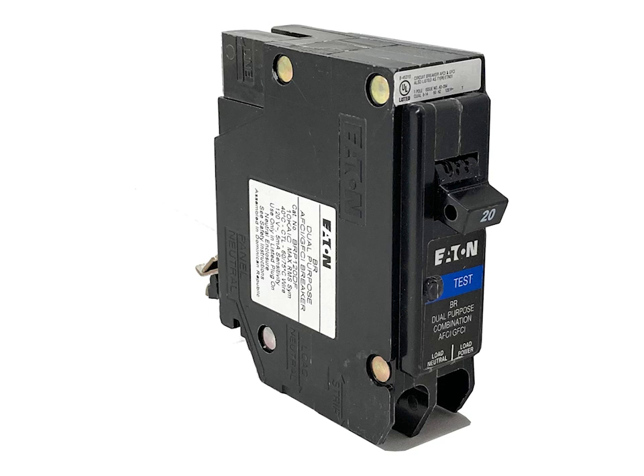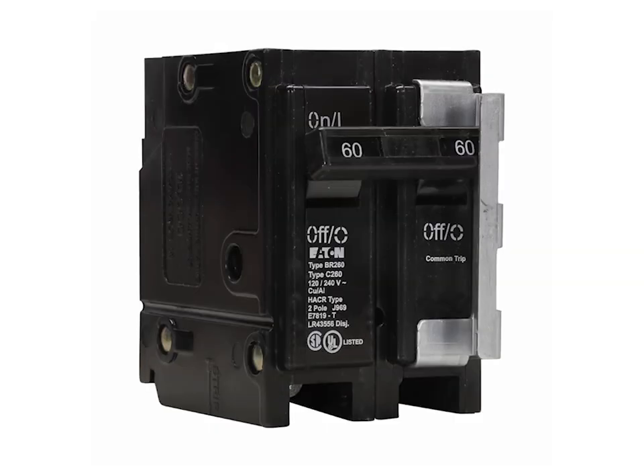Some unscrupulous home builders have traveling circuit breakers. They put in these code-required expensive breakers to get through inspection and then remove them, replace them with non-protecting breakers, and then take them to the next job site. This is bad on many levels: theft from the homeowner, code violation, etc. URLs are listed below for this information. There is also a requirement that some circuit breakers have lockout capabilities. The lockout is a small flange that attaches to your normal circuit breaker.